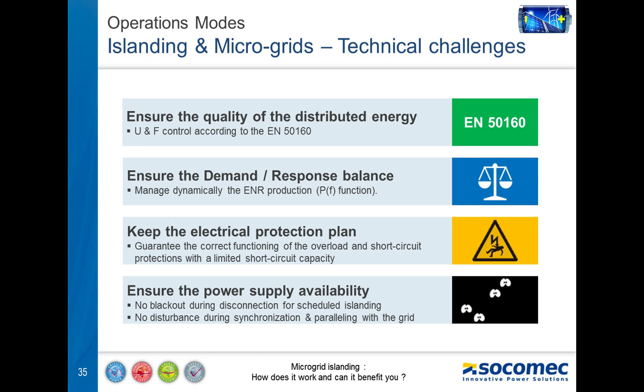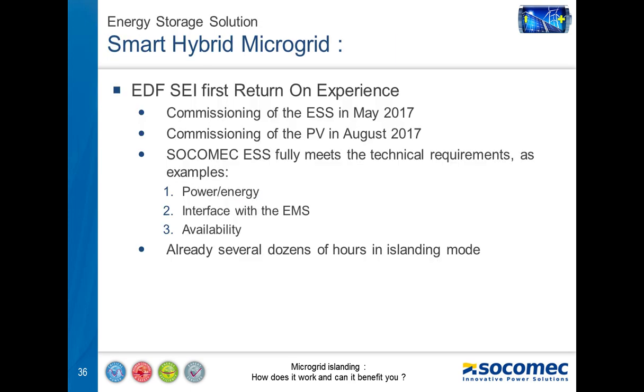The third point is to keep the electrical protection plan. In comparison with the short circuit capacity of a real grid, when we switch from the genset to the PCS or from the PCS to the genset, we have to ensure that all the protections distributed on the microgrid are correctly tuned according to the short circuit power capacity. This part has been validated by EDF R&D during the Nice Grid project. And the last is to ensure the power supply availability and quality, but logically with power conversion, it's, I would say, a standard feature.